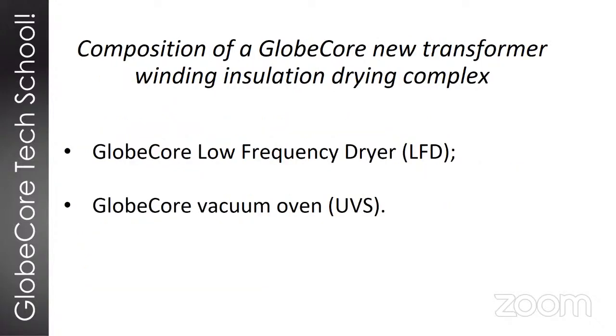Thank you. So the first combination we're going to look at is a combination of LFD plus a UVS. UVS is the vacuum oven that you put the transformer core into. So before the process begins, the core of the transformer is placed into the oven, and then the LFD heater is connected to the transformer winding. In the process, moisture goes from paper insulation into the chamber of the oven, and then a vacuum system removes that moisture from the oven.